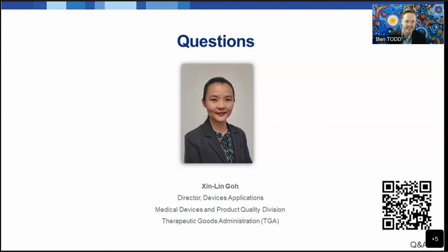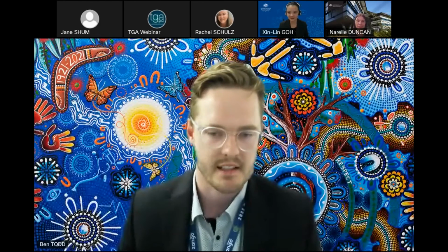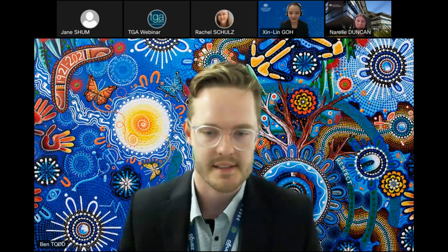I'll take this one. I'll give Xin-Lin a well-deserved break. So for these, obviously, the certificates cannot be reissued after May of last year. So this is where we would only be accepting evidence from the notified body. So the notified body needs to basically prove to us that the change is non-significant.